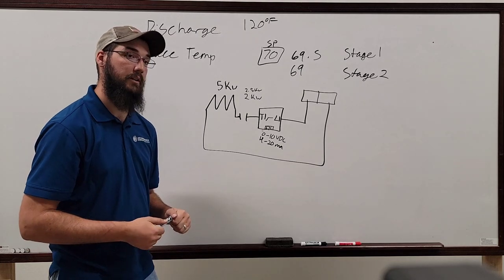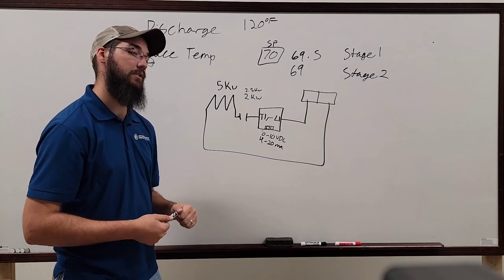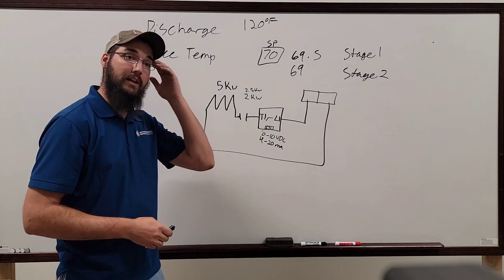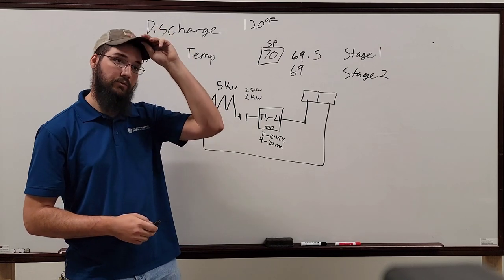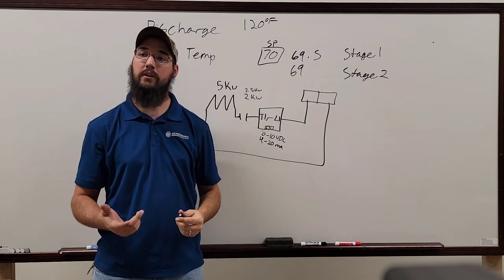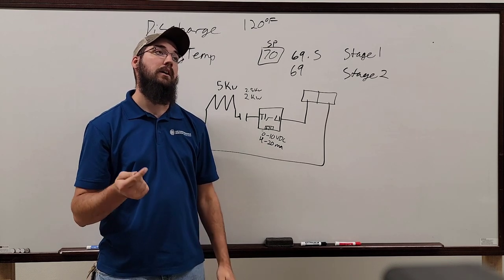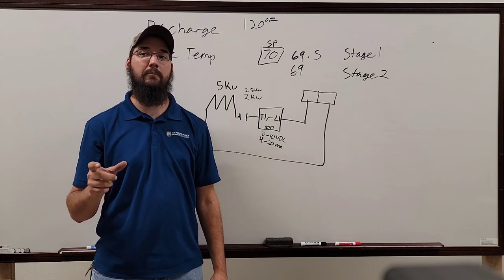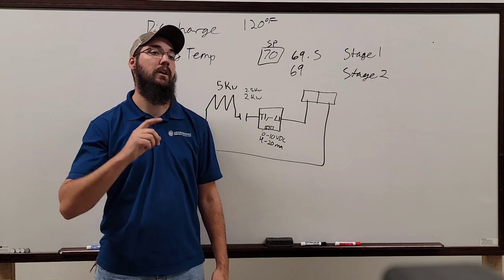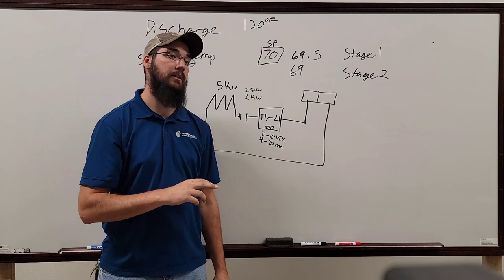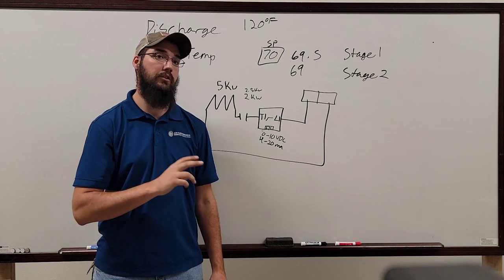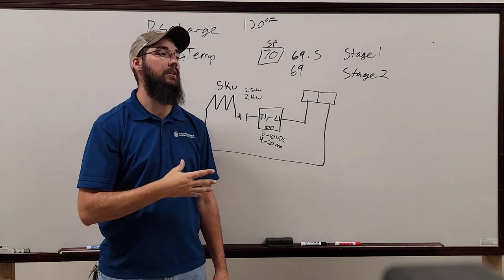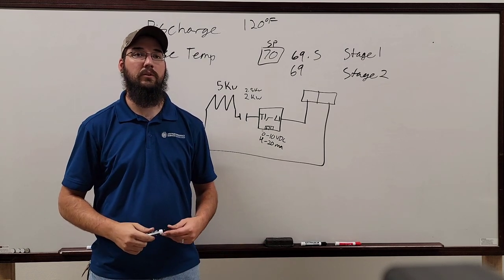They're very expensive, by the way. They're not cheap to buy, especially the three-phase versions. Typically, not always, but many times, like for Titus, for example, any of the Titus fan power boxes that I've had to work on that have a three-phase heater in them, the distributor doesn't carry those heaters. They have to be specially built every time. So every time I've had one fail, most customers will usually buy two or three at a time, which are usually several hundred dollars per. And they'll have to put the order in, they'll manufacture them and then send them in. And it takes several weeks to a month or two. So just keep that in mind.